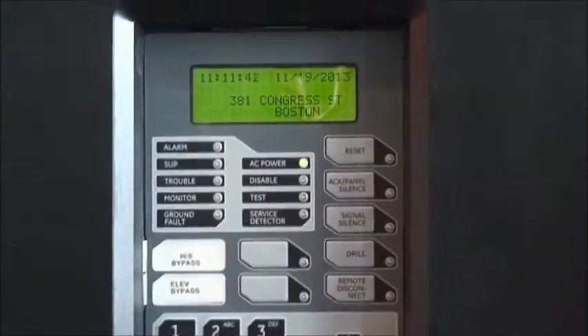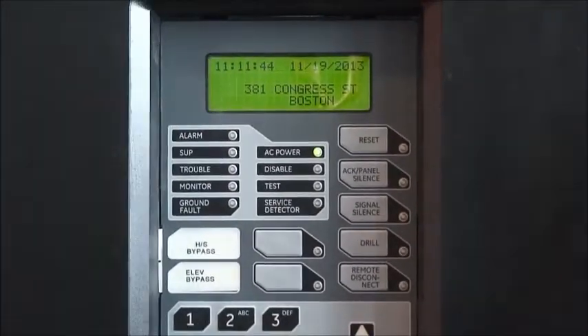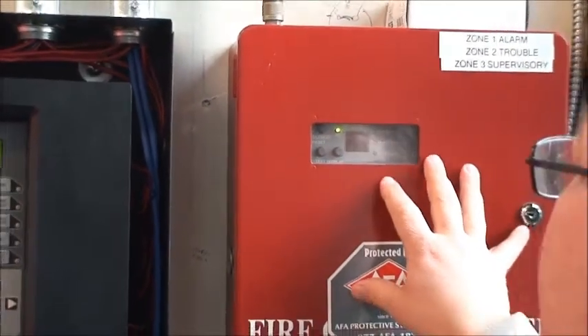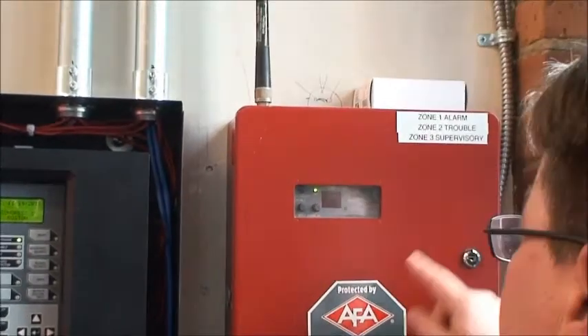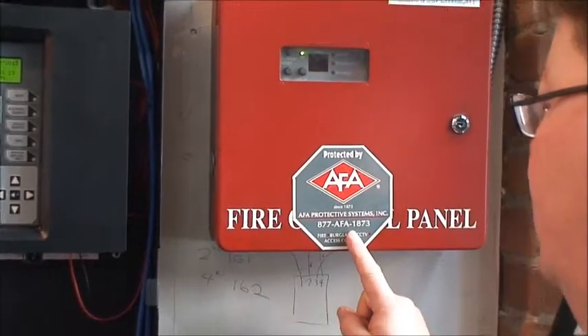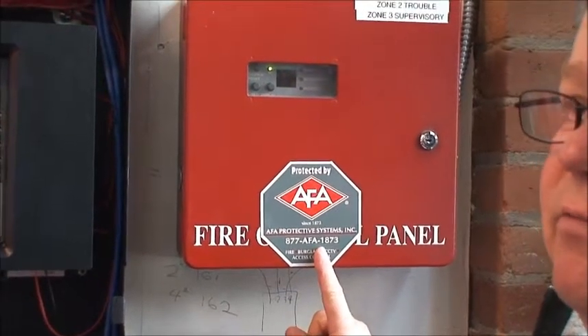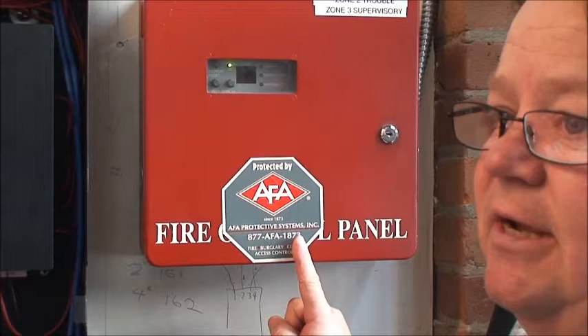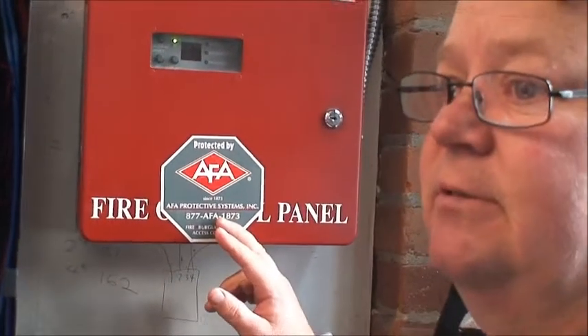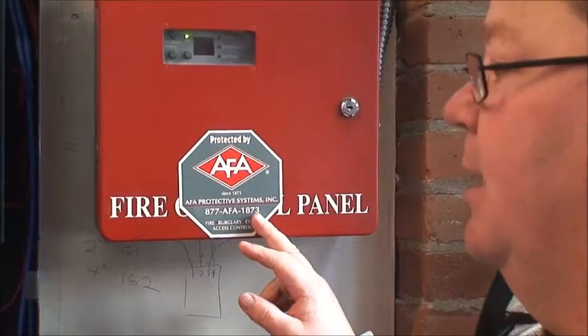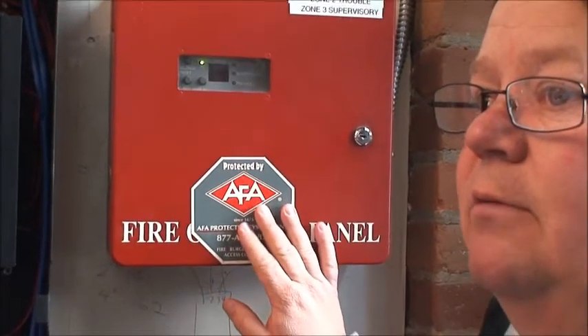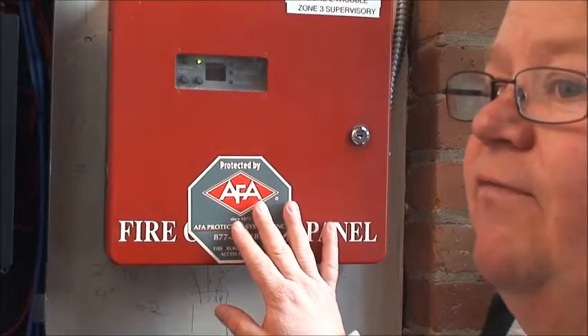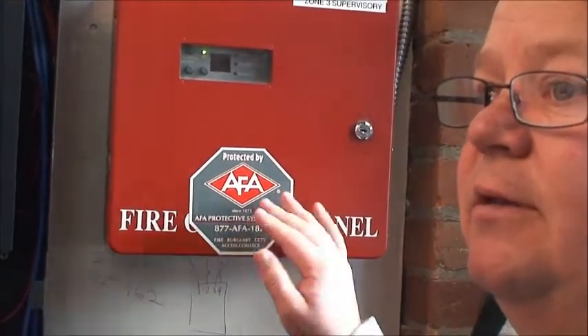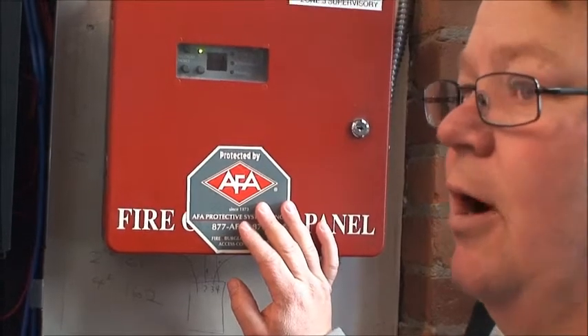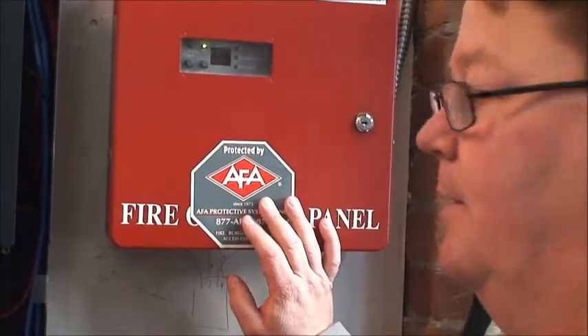If there's a trouble, for any reason it goes into trouble, it will send a trouble circuit signal to this panel, which will get relayed to AFA. You guys already have a contract with AFA that was set up previously, so we stayed with the same contract. They monitor this through AFA. They have the list that they would call, unless that needs to be updated between the owners. You guys can just update the new contact, because they don't want to call us, they want to call you guys from now on. So you may want to do that.